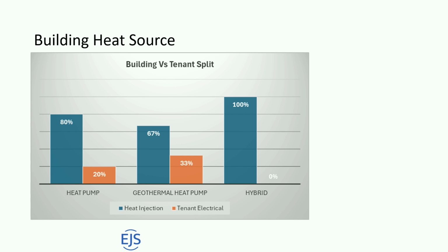Geothermal, a lot less on the building side, since I don't have the same size cooling towers and boilers. At the apartment level, in heating mode I have a lower condenser water temperature, so it's less efficient, and it does actually add a little bit of utility at the tenant level. And then the hybrid system, all I'm doing from a utility perspective at the tenant level is running a fan, because I'm getting hot water, it's a fan coil. The building is working extra hard because I'm running boilers and trying to get that temperature up.